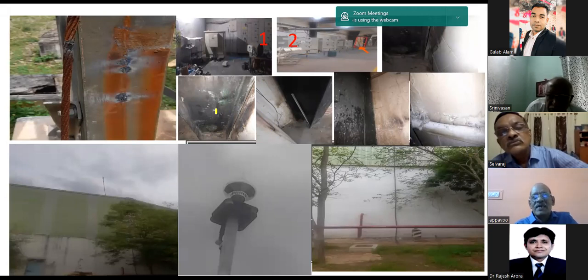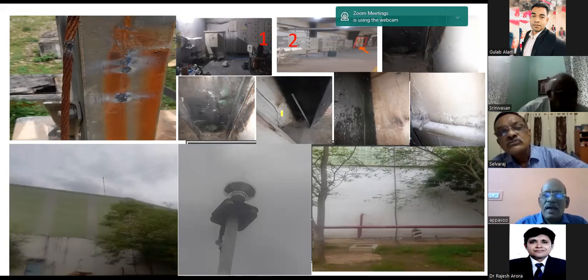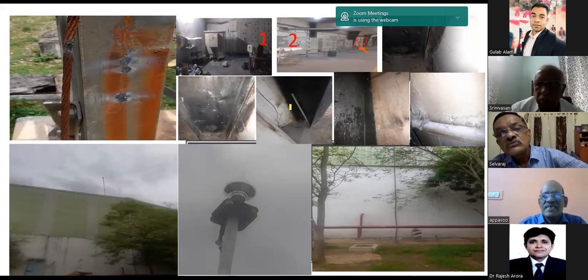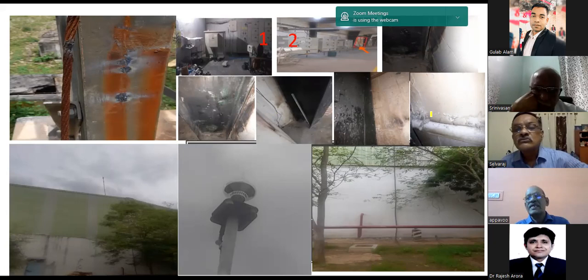You can see the impact of burning here much. And you have to see the depth of burning and the impact of burning on every place possible. So the burning is more at the beam side, facing the corner side, auto corner side. And the burning is less at the side facing the switchboard side. And also there was no power during that period.